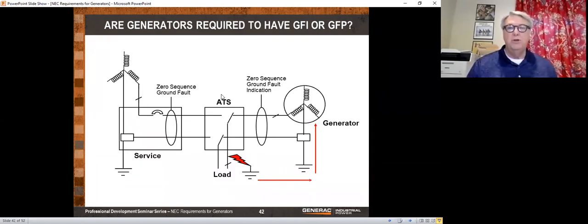This shows you a 4-pole transfer switch. And in this case, you can see that we have a zero sequence ground fault indication. So current goes out here. This would actually be 3 separate switches, but we're just showing one phase. It comes down through here, and let's assume that there's an actual fault where it goes to ground. Now, in order to get back to the generator, it has to go through here, and therefore the current goes through the zero sequence, but it doesn't come back through, so this detects an imbalance and it will trip.